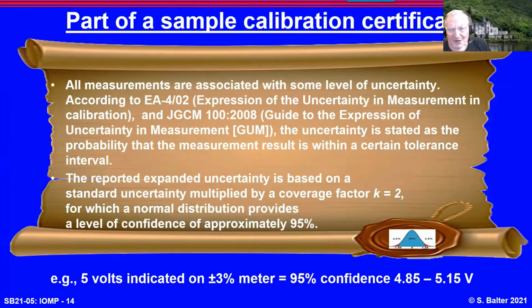This is a piece of a calibration certificate, and you see how it's described, the traceability to these documents. Essentially, all of these documents are available online, should you care to read them. If there's questions as to the calibration beam, my recommendation is you talk to the calibration laboratory, get some better description of the calibration conditions. For this particular one, the statement is they're using the expanded uncertainty K equals 2, as I've just described. So the confidence is 95%. So our indicated 5 volts, there's a 95% confidence that it's between 4.85 and 5.15.